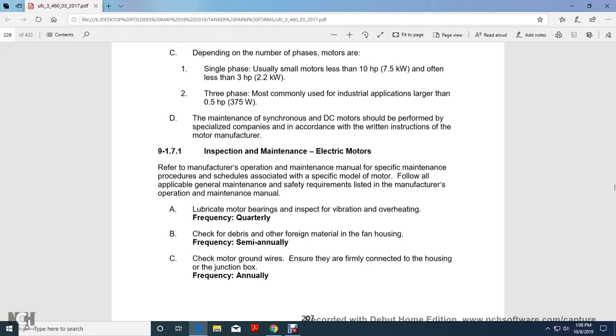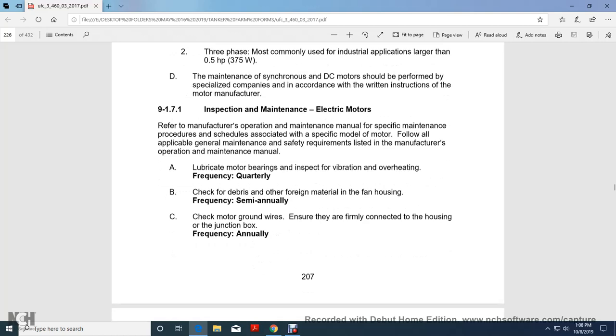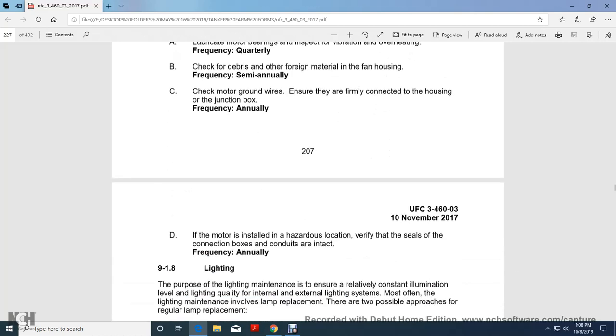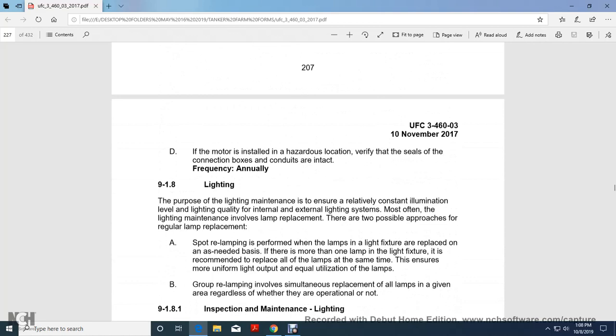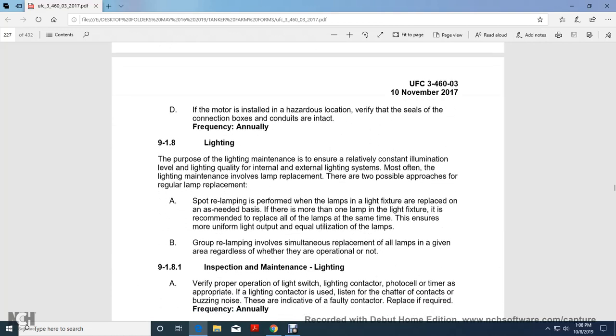Lubricate motor bearings, inspect vibration and overheating quarterly, and check for debris and other foreign material in the fan housing. Semi-annually check the motor ground wires and ensure that they are firmly connected with the housing and the connection jacks annually. If the motor is installed in a hazardous location, verify the seal of the connection box and conduits are intact annually. Lighting. The purpose of lighting maintenance is to ensure a relatively constant illumination level and the lighting quality of the internal and external lighting system. Most often, lighting maintenance involves lamp replacement.